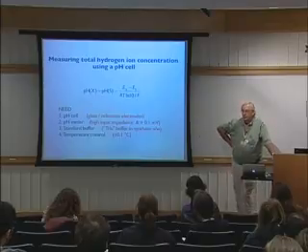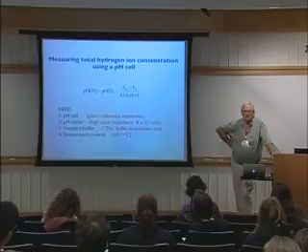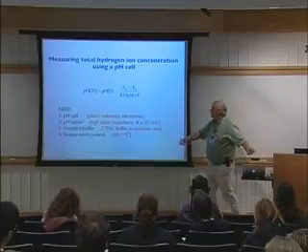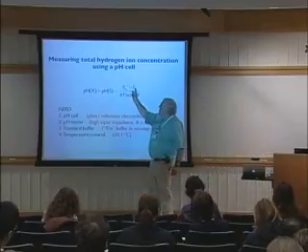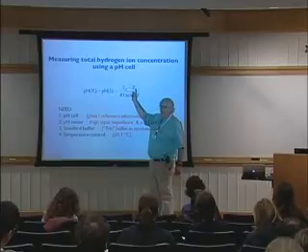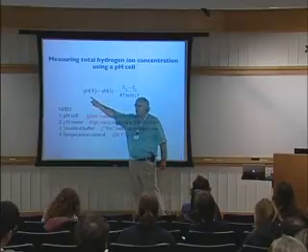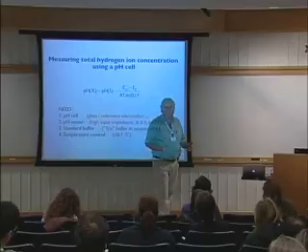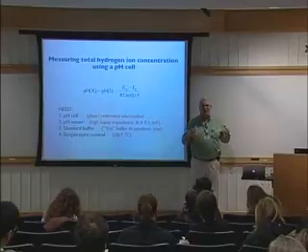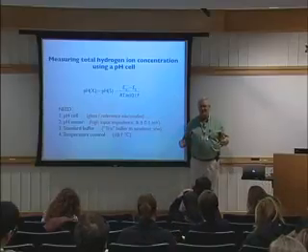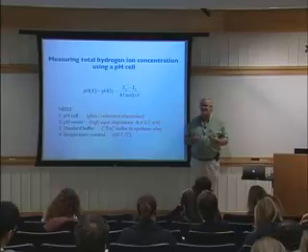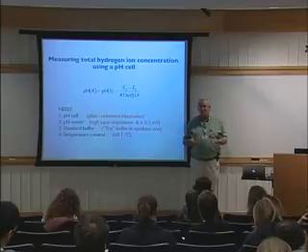Temperature control, you have to have some way of doing this. If you're not controlling temperature, that is, if these two measurements are made at different temperatures, and those buffers are actually acid-base systems, so the pH changes as a function of temperature, this nice, straightforward formula doesn't work.